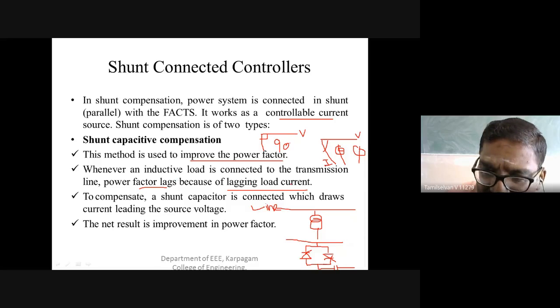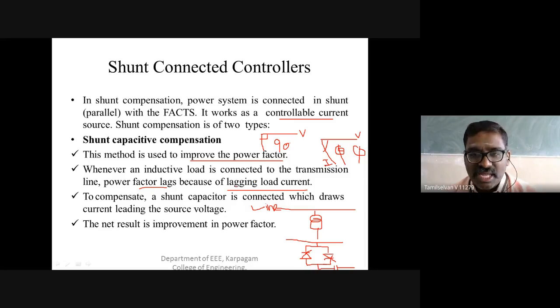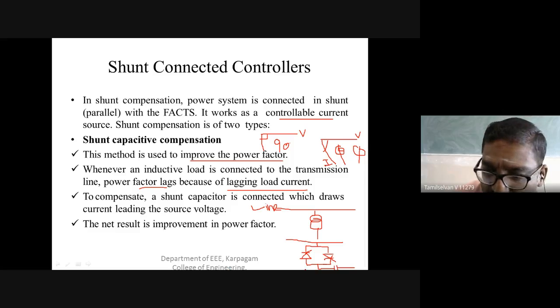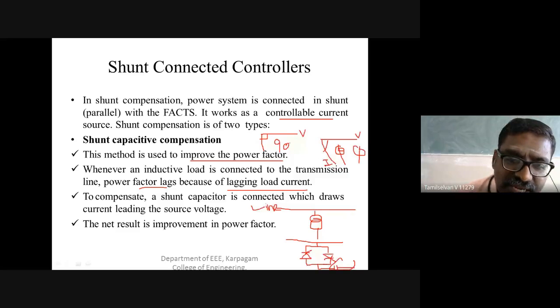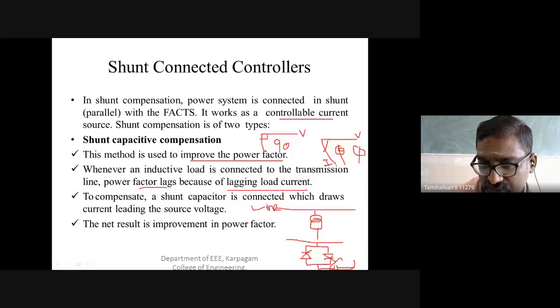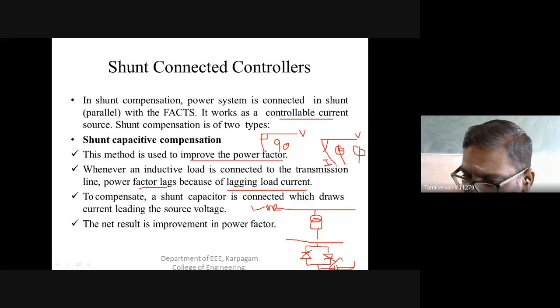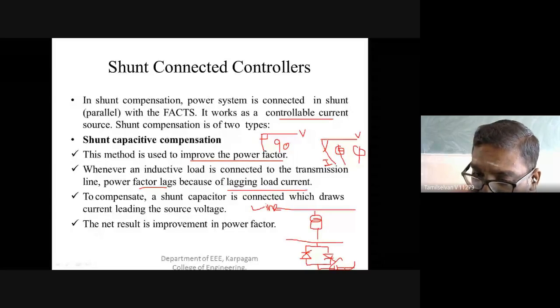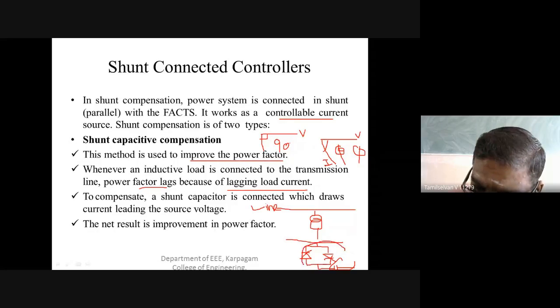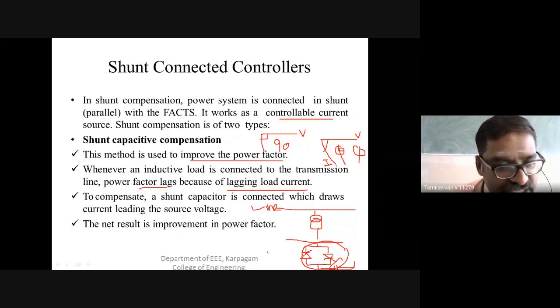Normally, whenever an inductive load is connected in the power system, the power factor will lag. Because of this lagging load current, that lagging component can be compensated by adding a shunt capacitor, so that it draws a leading current component relative to the source voltage, improving the power factor. So how much current has to be injected into the transmission line by the capacitor is decided by our power electronics component, the thyristor.